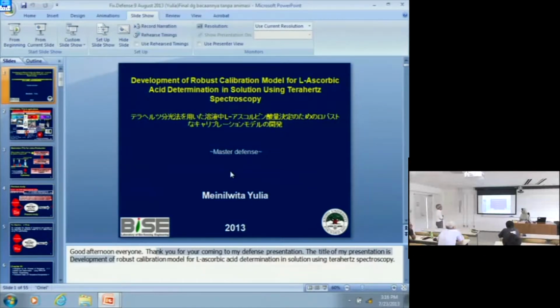Yes. As far as I know, robust in my study means that the calibration model I developed can compensate for any kind of disturbance, like temperature variation or other interference in complex solutions like glucose and so on. So by developing the robust calibration model, I hope I can compensate for variations, for example, of the temperature of the lamp, aging, and so on. Especially temperature. Yes, in chapter 3, I explained the robust calibration model for temperature compensation.